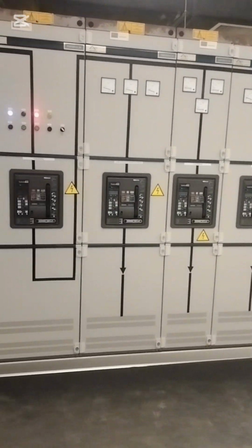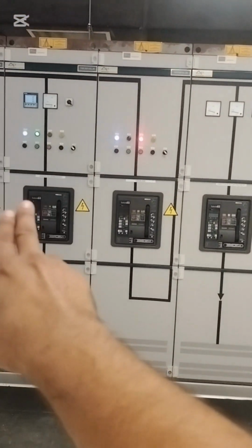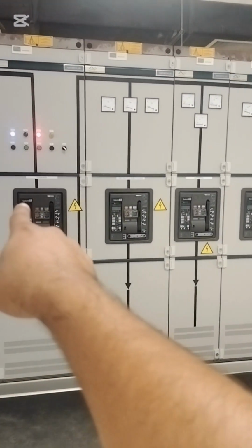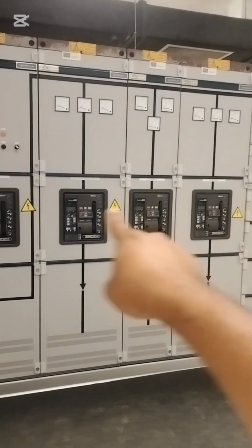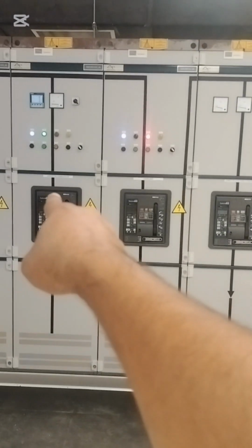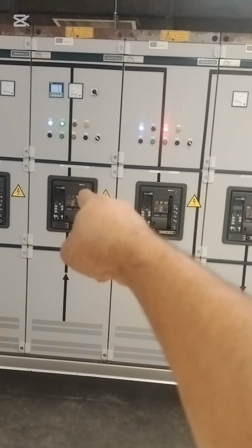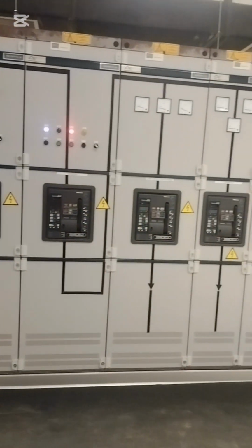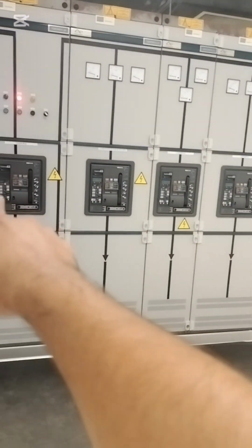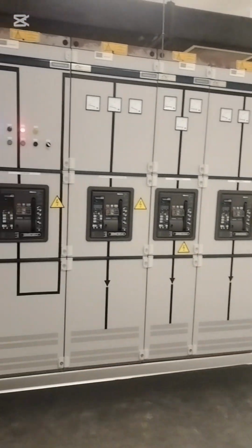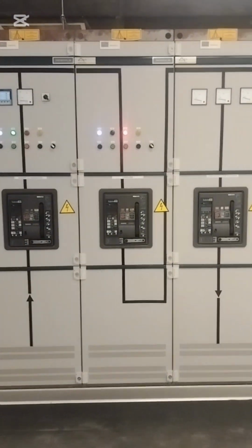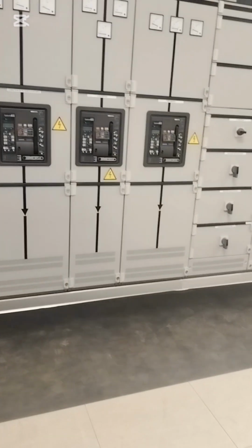So we need to be sure, because there is an interlocking between these 2 incomers and also the bus coupler. Okay, when they are all in open condition, after that we can make this breaker on. Otherwise we cannot make this breaker, because the control supply is interlocked from L1, L2 and incomer 1, incomer 2 and this coupler. When they all have healthy circuit supply, after that we can close this breaker. Okay, so this is the sequence of the LV switchgear room.